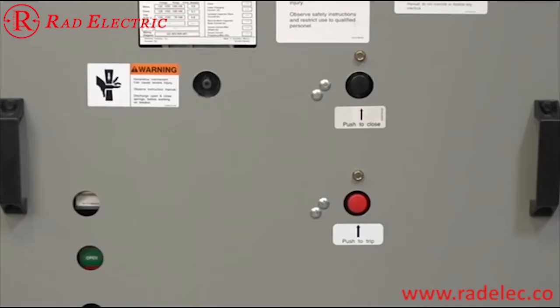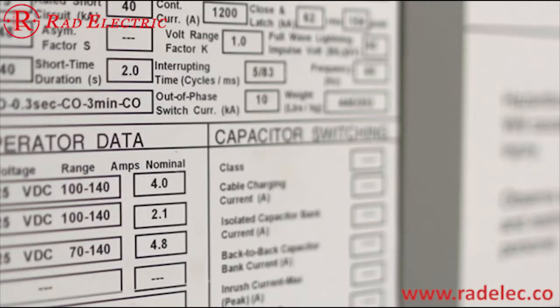Now, let's take a look at some of the features on the front panel. The label has important information related to the circuit breaker, like the breaker model number, serial number, rated voltage, interrupting capacity, continuous current rating, as well as the ratings for the trip coil, close coil, and motor. If you have any questions about the circuit breaker or experience any issues, email a photo of the label or provide the serial number of the circuit breaker along with your order information to a Siemens customer service representative.